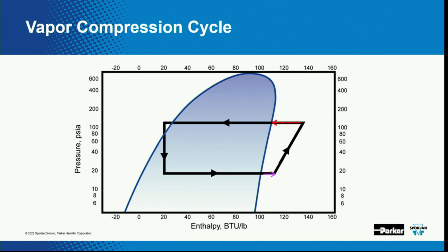If it stopped condensing right here, then we wouldn't have the liquid that we need to feed the expansion valves. So it goes all the way over till it's completely liquid, subcooled even, and then we drop it through that expansion valve, and that expands it so it goes from high pressure to low pressure. It goes from a tight liquid line into a big evaporator coil, and that expansion drops the pressure down, and that's where the cool happens.